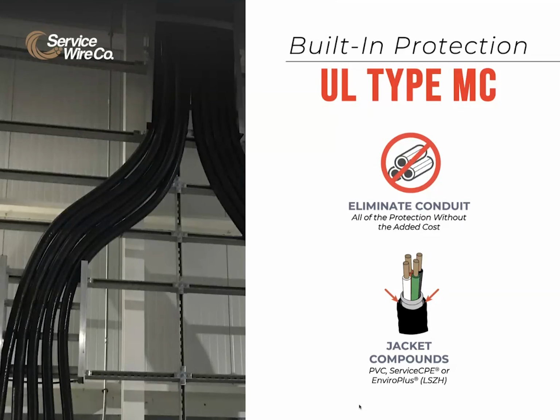For example, we've seen auto installations where the Type MC cable is cleated to the wall every 6 feet per the NEC code instead of fixed in conduit. This allows the facility to raise the cable up off the ground, but not be permanent, as the cable can be moved if the facility adds another line to their process. In addition to installation advantages, Type MC can offer some significant cost and labor savings.